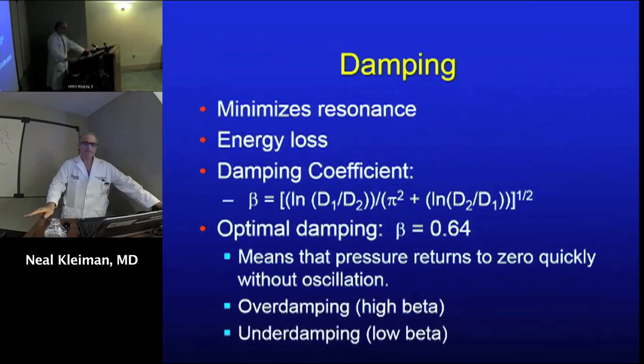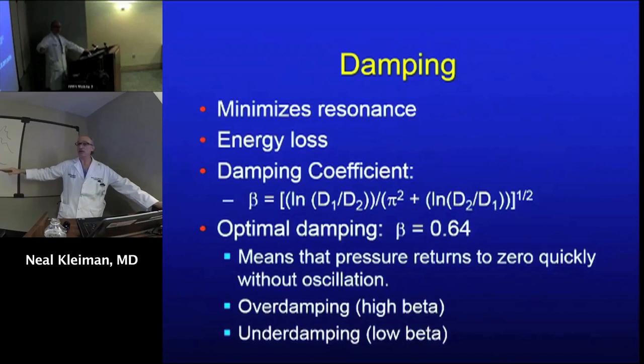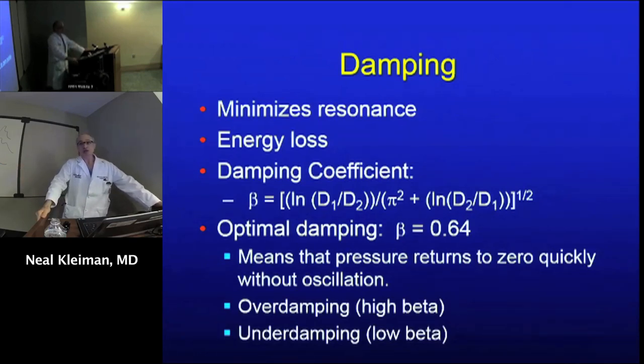So when we talk about damping, we're talking about the ability of a transducer to measure pressures, and the ability of the system it's connected to, to transmit pressures. Damping minimizes resonance, and resonance is really over-damping's opposite. As you get close to the fundamental frequency, resonance means you're amplifying those small components. It's a bit like the story of the bridge in Tacoma, which had a fundamental frequency that the wind happened to hit, and it started swaying a little, then a lot, then it broke and collapsed. That's what resonance is, and that's why you'd want something to damp those vibrations.